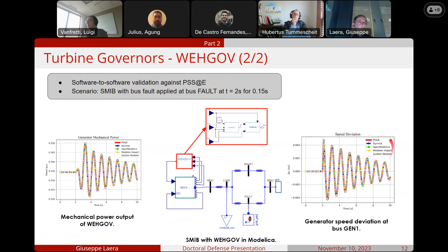The software-to-software validation of this component against PSSE has been performed with the single machine infinite bus system introduced before, with the WEHGOV component in it. The scenario considered for the simulation is a fault applied at bus fault at 2 seconds for 0.15 seconds. Here we have some plots showing the results. It should also be noted that the same model has been run in several Modelica-compliant tools.